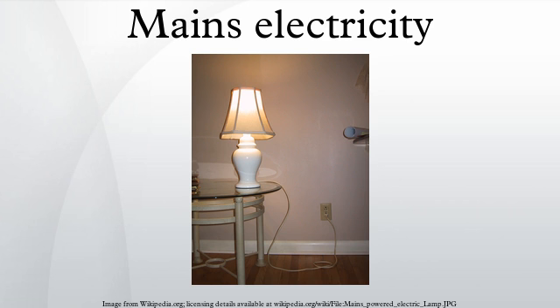Example size of earth cable: a 4 mm electric cable. A 4 mm size cable can be used for an electric oven. Cable sizes for power points are 2.5 mm, and for lights 1.5 mm.